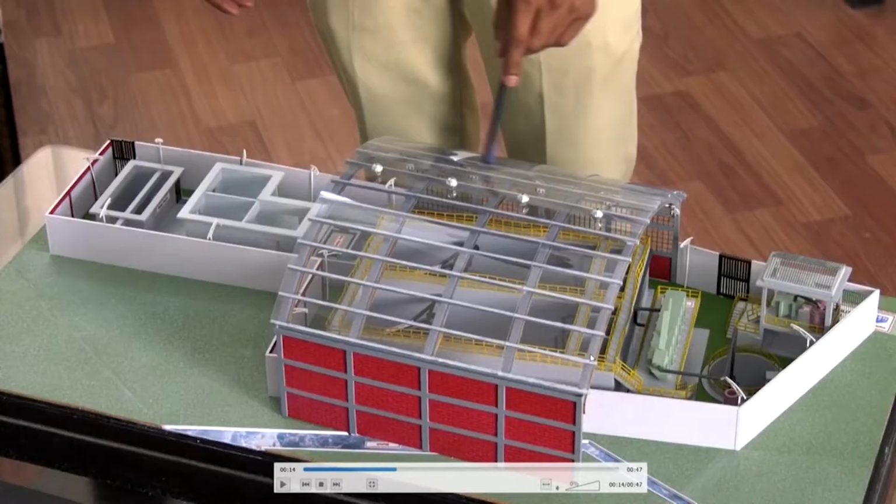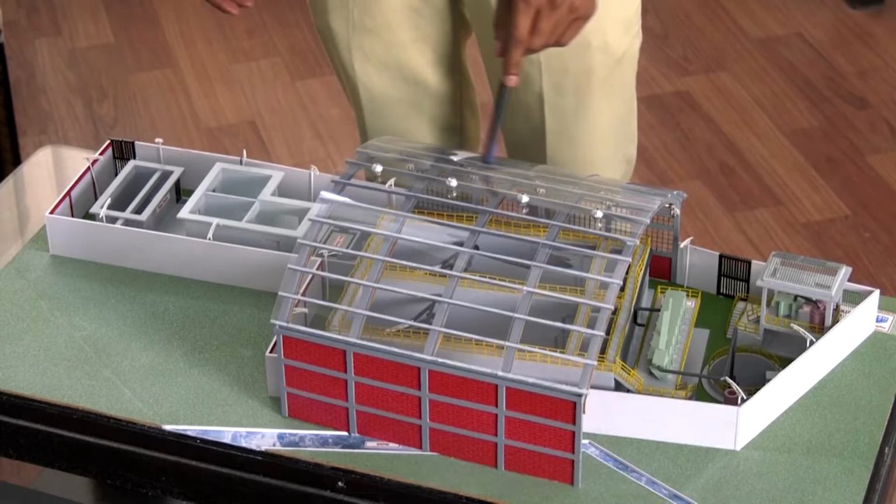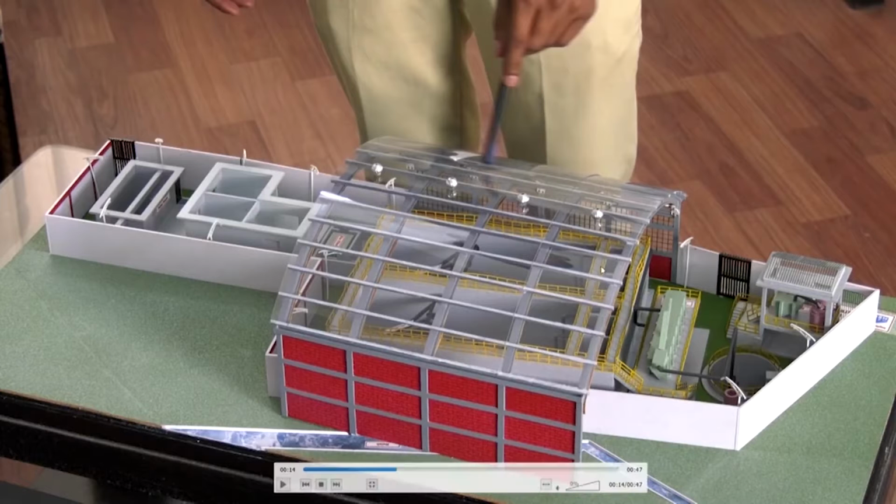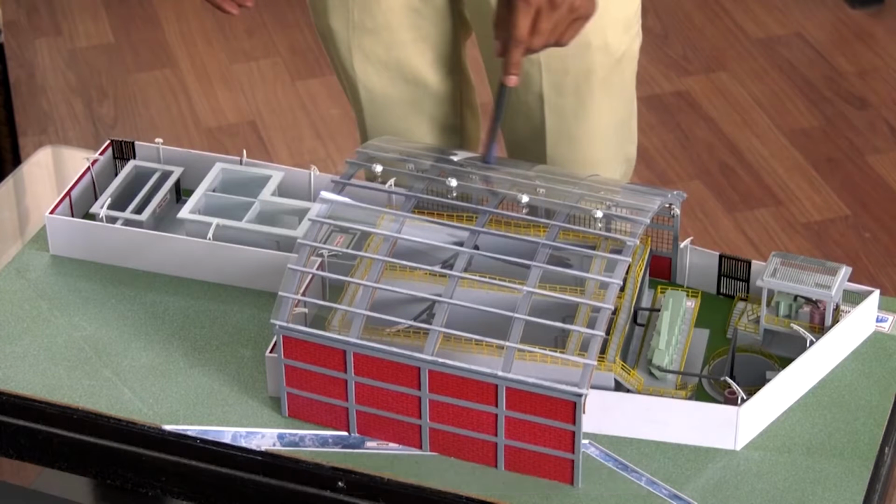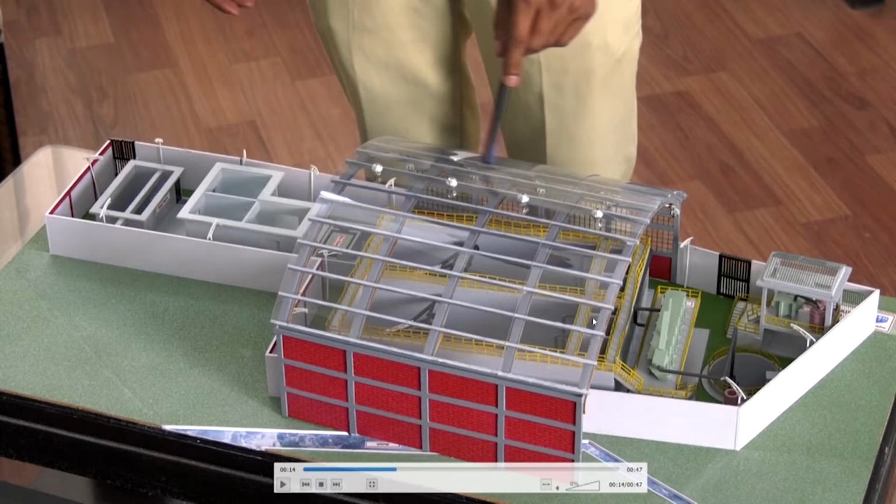That's what happens in these bioselector tanks. You want the kind of microbes you want to prevail to grow, so that's why you are creating high F by M conditions in this tank. You can't create that over the entire tank because then your effluent quality will be degraded, right? So you are now having these bioselector tanks.